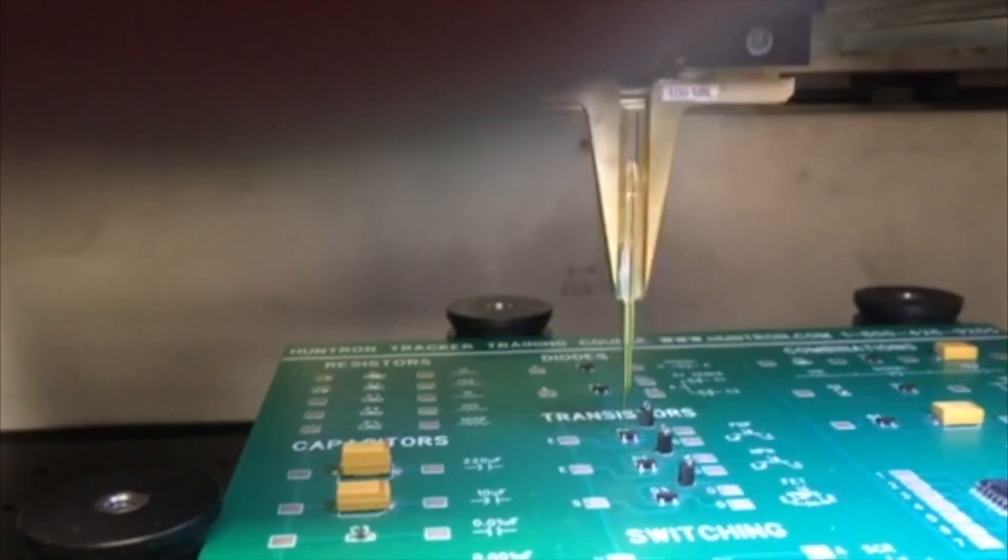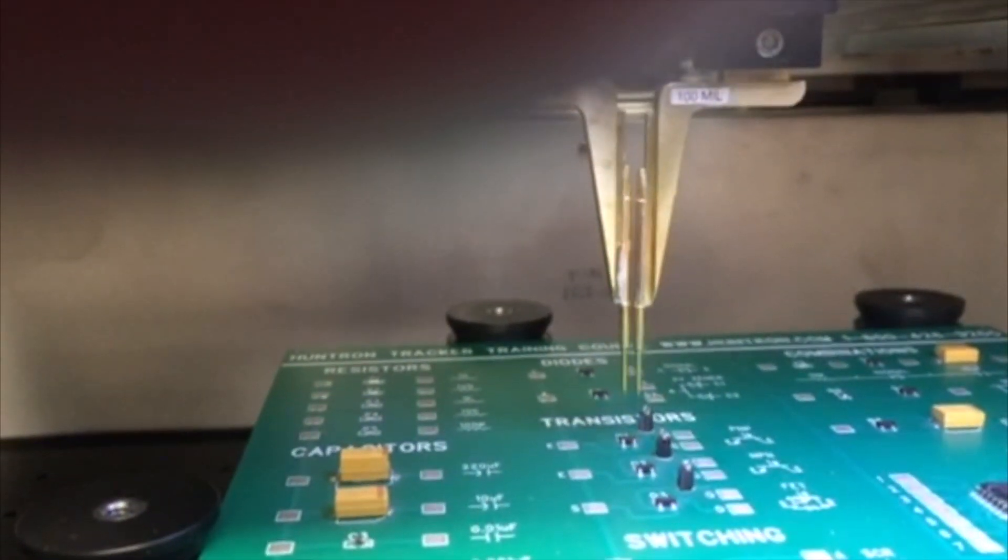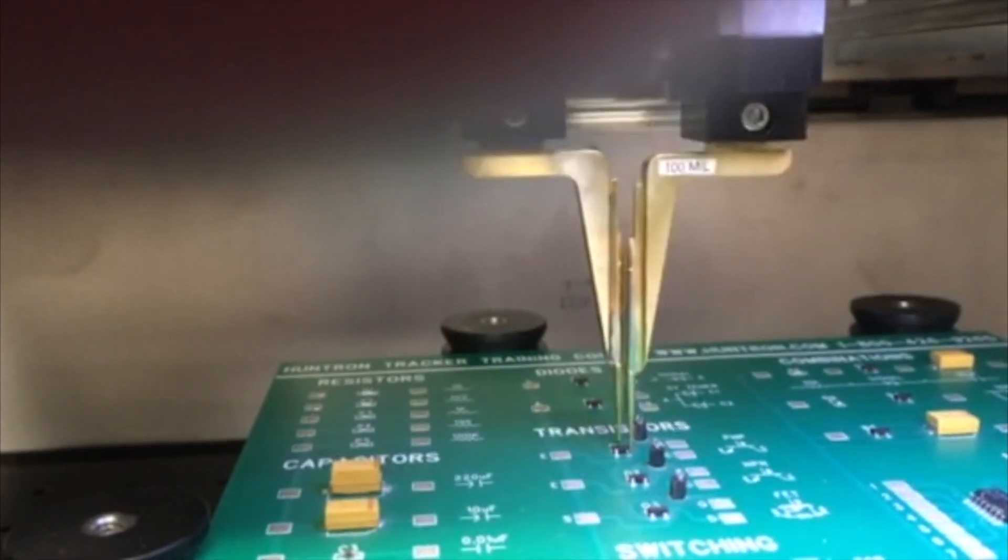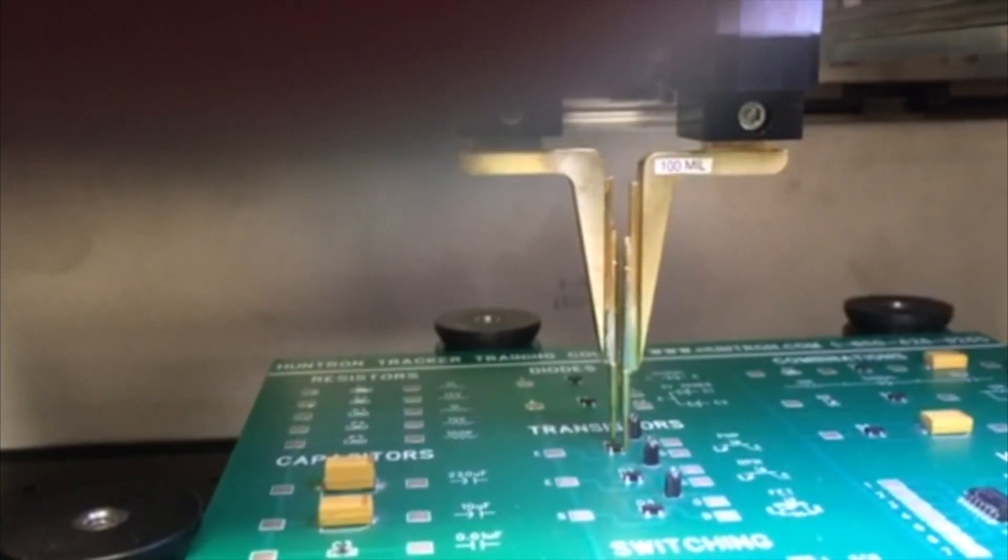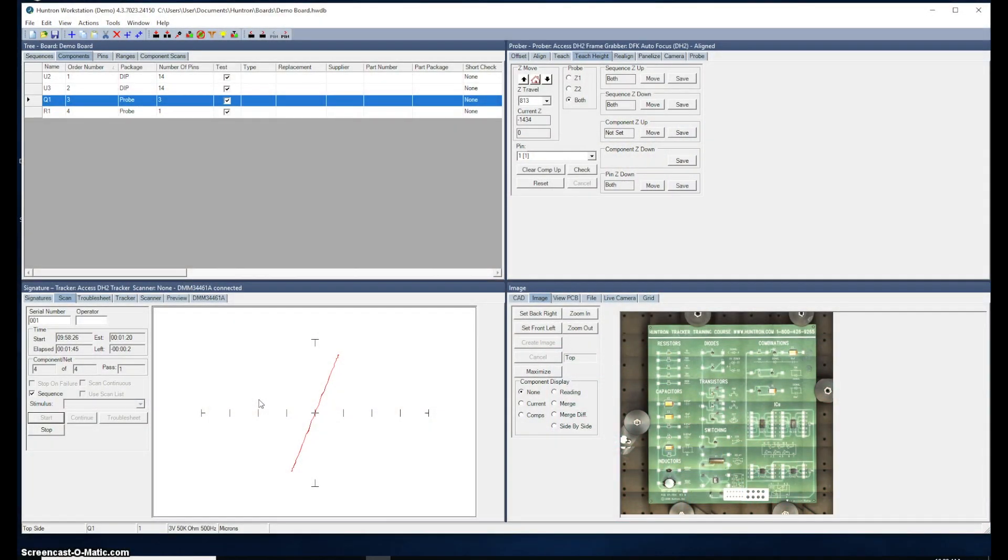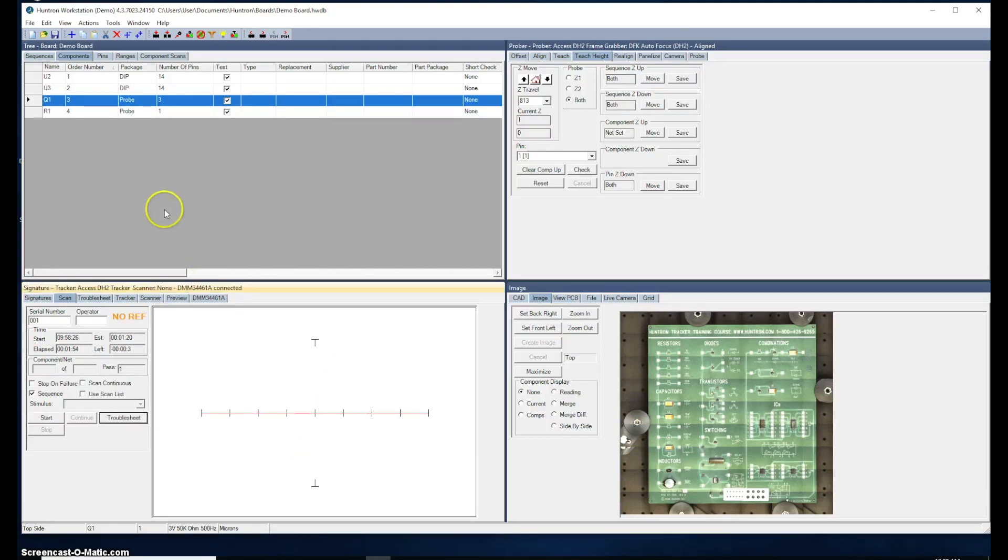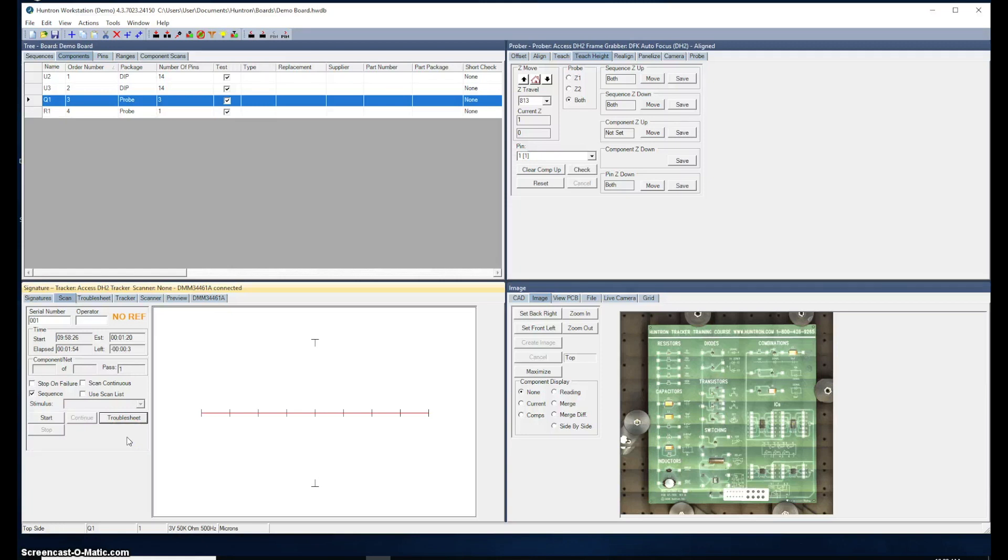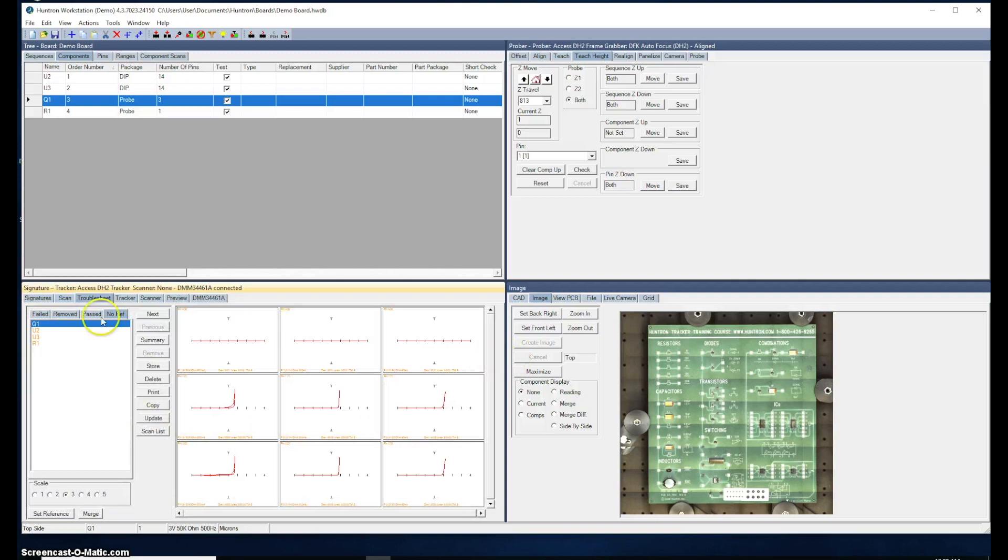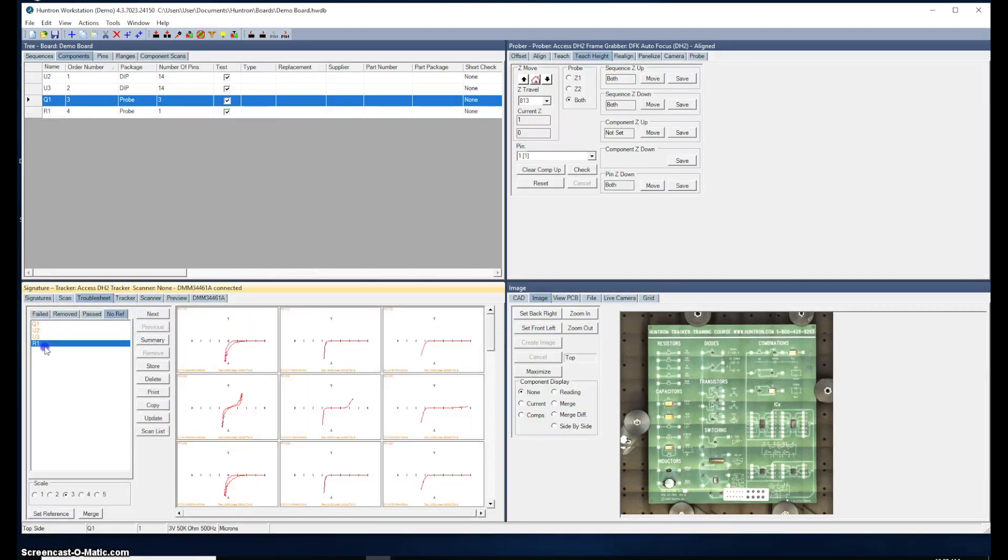Close to probe Q1. Notice how close the probes are together. It always gets a little scary when it does this. And then lastly, it'll go over and probe R1. Just two pins. Notice how close the probes are together, probes to each side of the device. When the probing is complete, it will give you a result. In this case, it should come up as a no ref. It means that there was nothing in the database right now to compare to because the way the system works is that you scan the signatures from a known good board and store those into the database. You can go to this troubleshoot button. Here are the signatures from our capture.